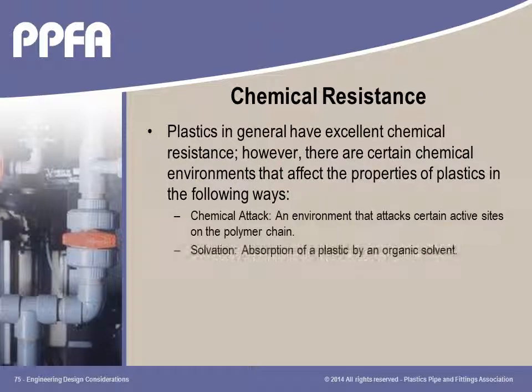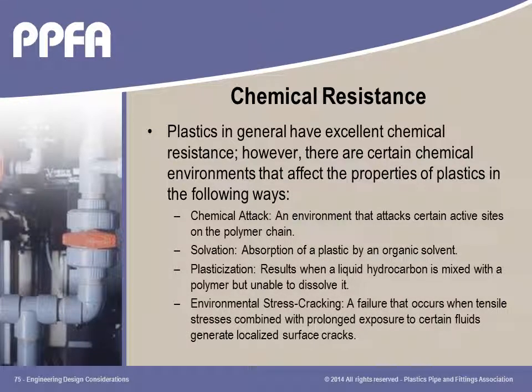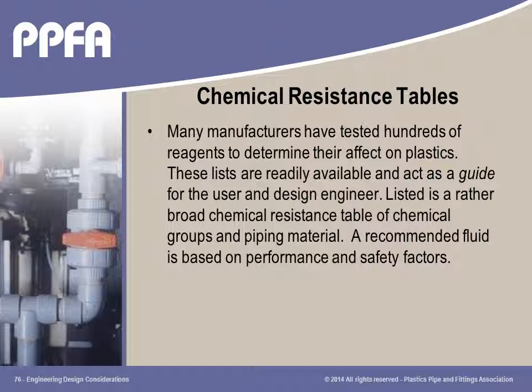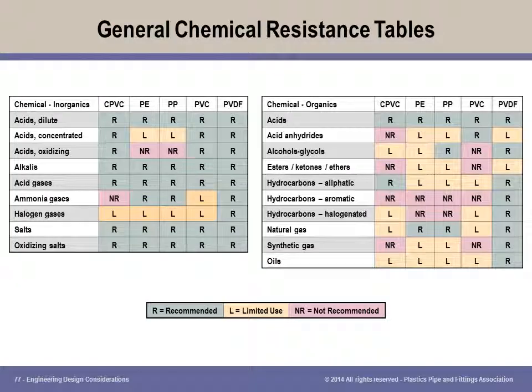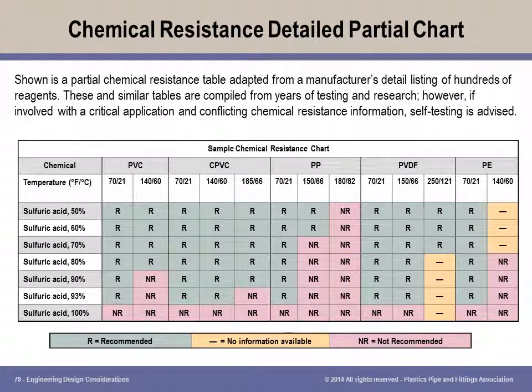A major reason thermoplastic piping is considered for industrial applications is its chemical resistant capabilities. This applies to both the fluid being transported and the outside environment. About 1,000 different chemicals and solutions have been tested by plastic resin and product manufacturers to assist designers and users as to which plastic piping material to select. In addition, chemical resistant tables are available for elastomeric compounds such as gaskets and O-rings that are used in sealing plastic flanges, valves, and pumping products. Although years of experience and testing have gone into the published chemical resistant data, it is highly recommended that designers and users verify these fluids for material compatibility.